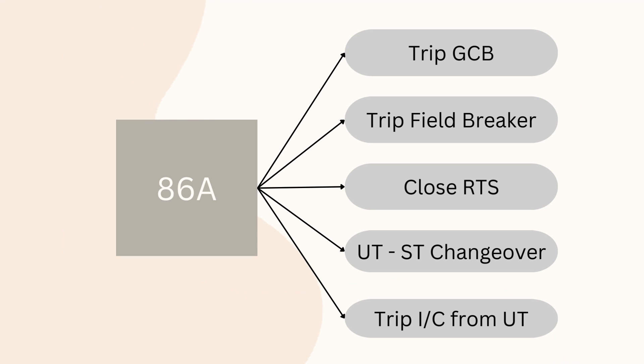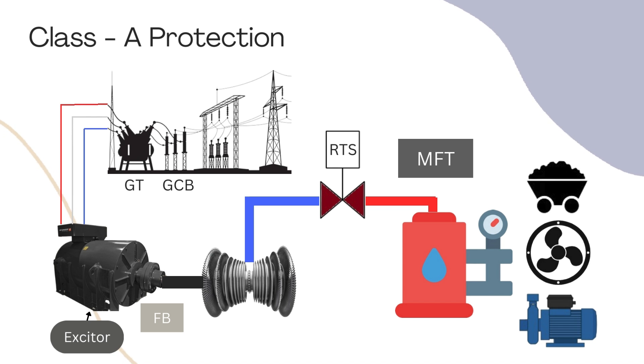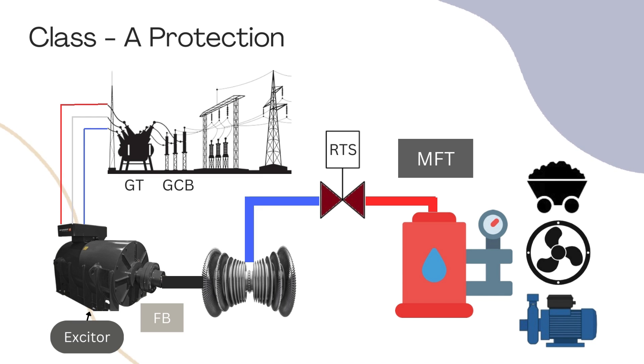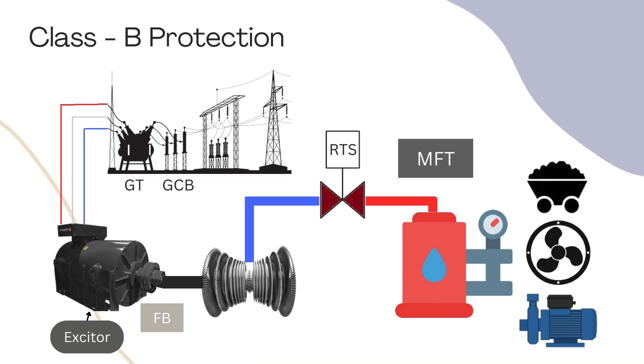In Class A protection, the trip command goes to the GCB, UT incomer, and RTS simultaneously. But there is a problem: when the turbine is tripped, there may be trapped steam, and due to the kinetic energy of the rotor it will take time to stop rotating and provide mechanical power to the generator — the rotor may over-speed. Another problem is that when Class A protection operates, power flow to the grid stops suddenly, creating a grid disturbance. This problem does not happen with Class B protection, where generation decreases gradually before the generator is isolated, allowing trapped steam time to finish.